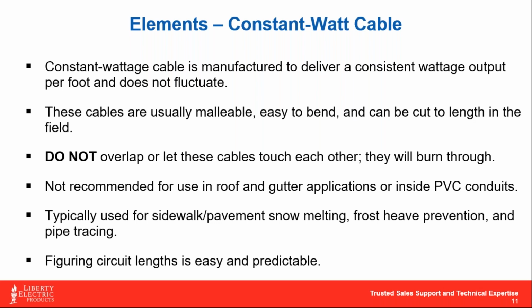And I'm going to give you a little tip on these real quick: if you want to have a cable where your cost per foot is down around 50 cents, which is what those are, so that you can sell them at retail for $1 a foot, the jacketing is often made with PVC. And one of the byproducts of heating that PVC up to a pretty good temp is chlorine, which takes the form mostly of a gas inside of the jacketing of that cable. And it becomes highly corrosive to the bus wire within the cable. So what happens is these cables will actually destroy themselves from the inside out over time.